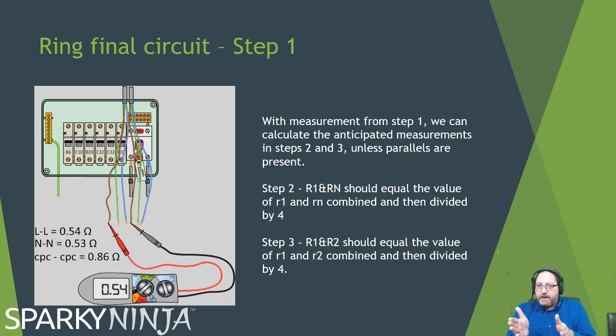So I'll go line to line at the board. If my line to line gives me open circuit, I know at one of these sockets the line has come out and I've got to fix that. I'll go line to line, get a reading. I'll go neutral to neutral, get a reading. I'll go earth to earth, I'll get a reading. And we record those in the lower case, little r1, little rn, little r2. If you look in the schedule of test results, you'll see there's a dedicated box for those. If it's a 2.5, 1.5, then the line and the neutral should be the same because it's the same size. The smaller earth size would result in an increase in resistance, and we have that ratio of 2.5 over 1.5. 1.67 is the multiplier to get from one to the other.